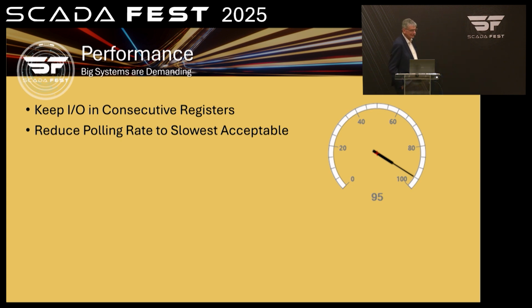Do you really need to see the tank level every second? It's not moving that fast, but you still have to poll it. And if you get 10,000 tags that you're getting once a second, that's putting a big demand on the system, eating up your disk space, logging any minute changes that happen. Can we get away with 5 seconds? 5 seconds is pretty good. That's 5 times faster, or 5 times more capacity you have in your system.